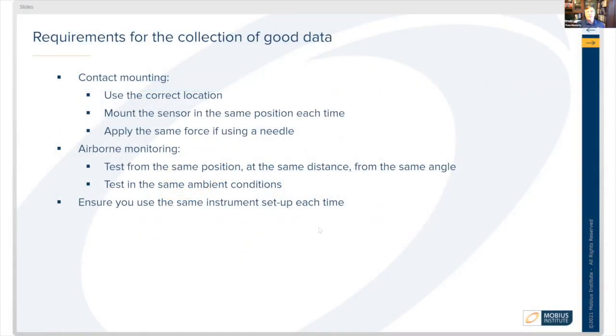For good data collection, requirements for contact mounting include using the correct location, mounting the sensor in the same position each time so data can be collected from the same position every time, and applying the same force. Magnets or threaded connections are best.